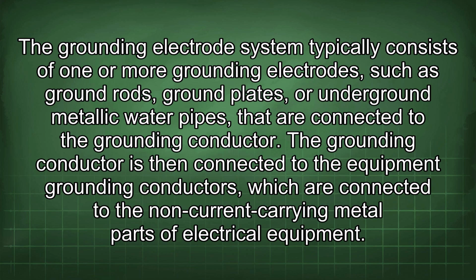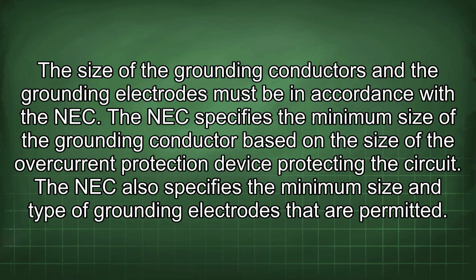The grounding electrode system typically consists of one or more grounding electrodes such as ground rods, ground plates, or underground metallic water pipes that are connected to the grounding conductor. The grounding conductor is then connected to the equipment grounding conductors, which are connected to the non-current carrying metal parts of electrical equipment. The size of the grounding conductors and the grounding electrodes must be in accordance with the NEC. The NEC specifies the minimum size of the grounding conductor based on the size of the overcurrent protection device protecting the circuit. The NEC also specifies the minimum size and type of grounding electrodes that are permitted.